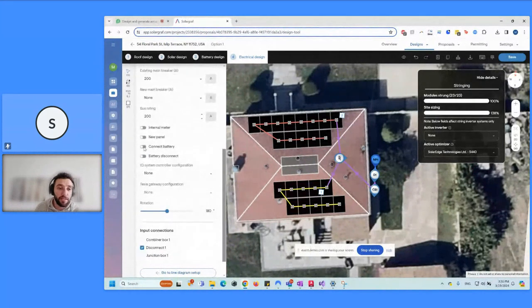We do have batteries in this instance, so hit connect battery. And then we have an additional battery disconnect, meaning if your battery is really far away from your system controller and your AHJ requires it, you can add another battery disconnect next to the battery.